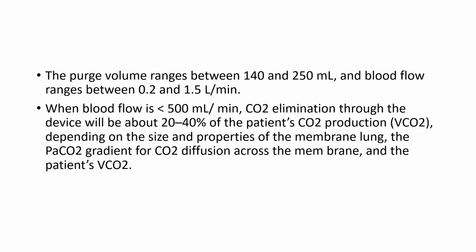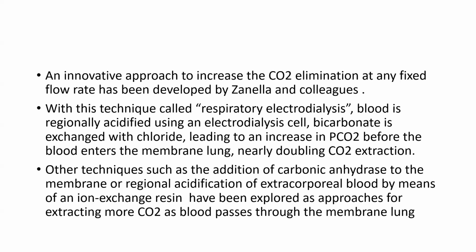Depending on the size and the properties of the membrane lung, the CO2 gradient for CO2 diffusion across the membrane, and the patient's CO2 production. An innovative approach to increase CO2 elimination at any fixed flow rate has been developed by Zanella and colleagues.